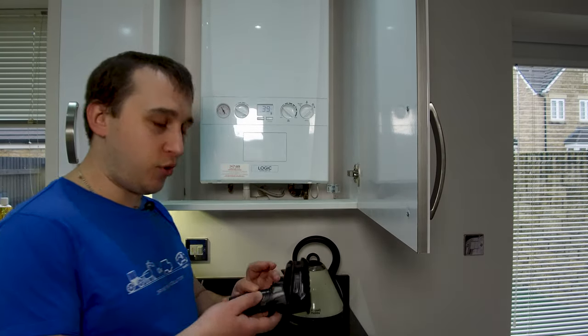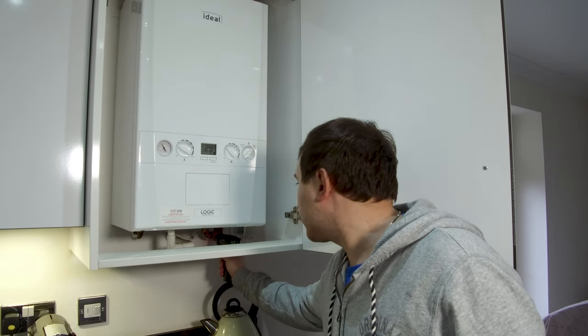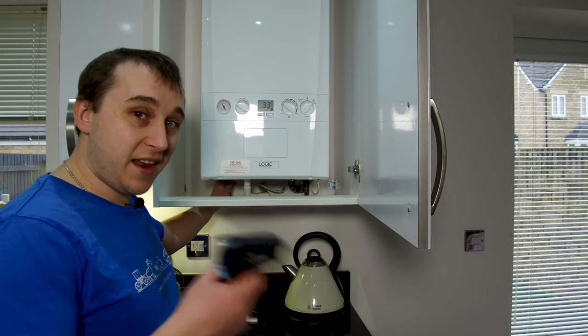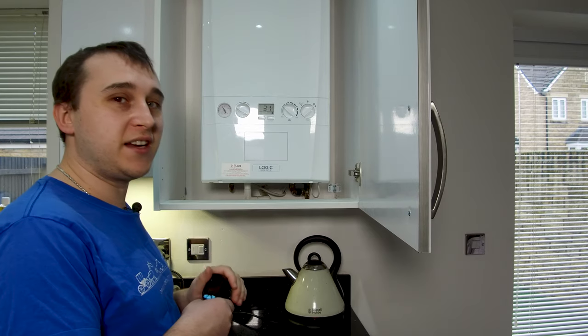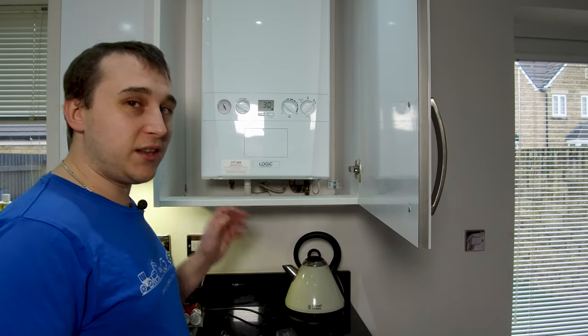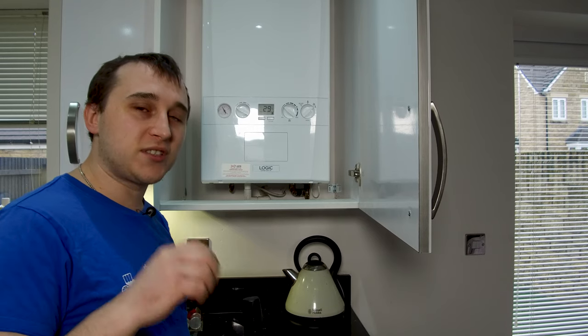To check temperatures I've bought a thermal infrared gun — I can just point this at anything in the room and it tells me the temperature. To get the flow and return pipe temperatures accurately, I've wrapped some black tape around the flow and return pipes underneath the boiler. I give the system a while to run, then point the gun at the black tape so it doesn't reflect, and I get a perfect reading. As you can see, it flows out at 30°C and returns at about 26.5°C — a perfect temperature for condensating and saving money. Links to the infrared gun, black tape, and all other products are in the description.